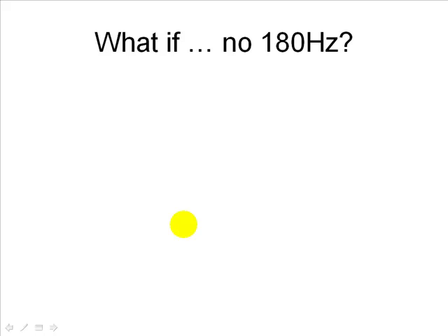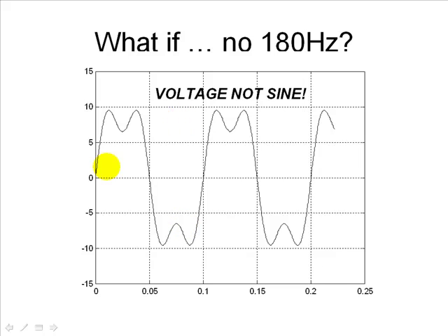What happens if there is no triple frequency in the magnetization current? Could be we filter it out, or we wire the transformer in a way that prohibits triple frequency currents from circulating. If that is so, if we have no triple frequency in the magnetization current, then the flux will be distorted, and the induced voltage will not be sinusoidal anymore. The induced voltage will look like this. It's not a sine.